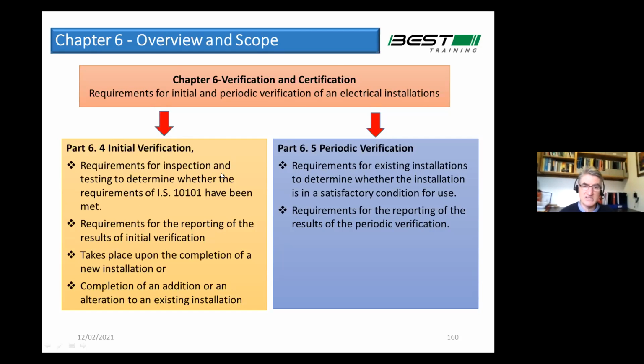For example, before energization, you've got to check the continuity of certain conductors, especially the earth conductor. Make sure you have an earth connected to every location. That's very, very important. Ring circuits, you've got to check for continuity there. You've got to check for polarity before energization. So go around and make sure all sockets are correctly wired, etc. What else do you do?